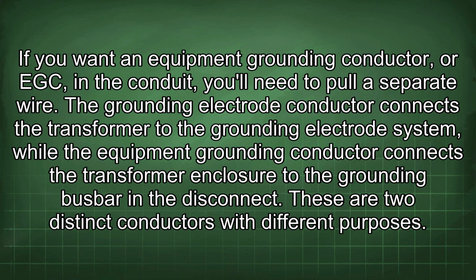The grounding electrode conductor connects the transformer to the grounding electrode system, while the equipment grounding conductor connects the transformer enclosure to the grounding busbar in the disconnect. These are two distinct conductors with different purposes.